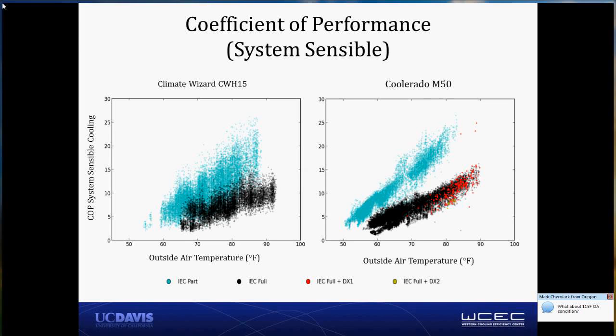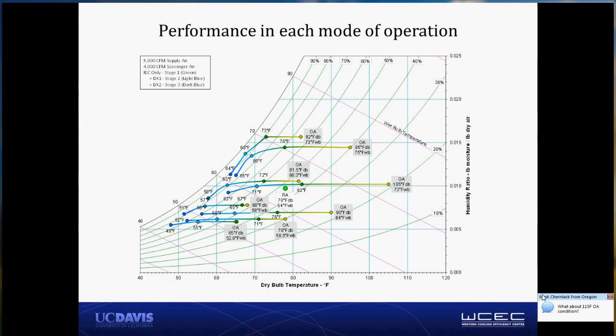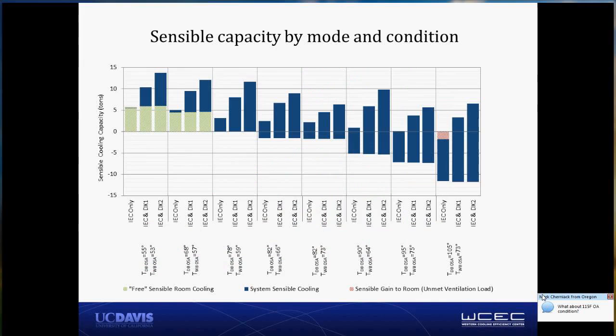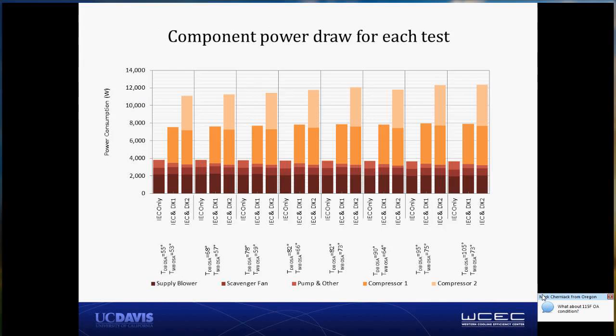wondering why we didn't mark out performance at 115 degrees. Yeah, that's marked out as sort of a peak operating point, especially by DOE's rooftop unit challenge. We didn't include it here mostly because there's very few locations in California that will reach 115 degrees. We think that you can extrapolate fairly well for the performance of the indirect evaporative system out to that point, and honestly, we just had to constrain the number of points and tests that we had included here.